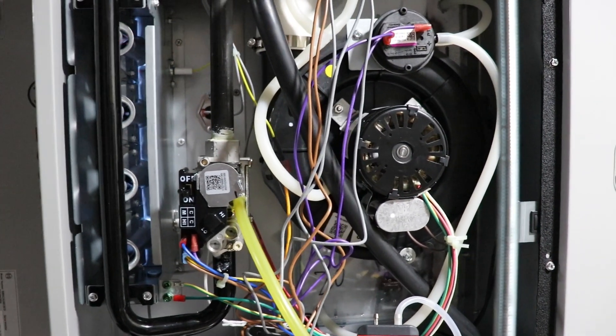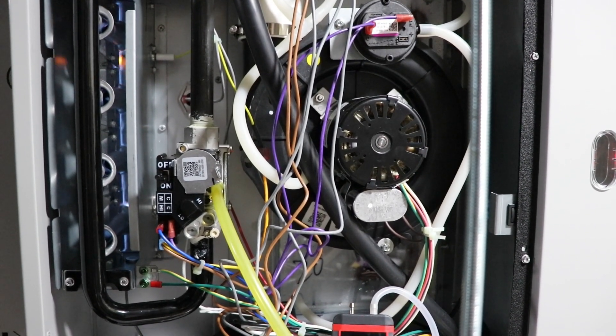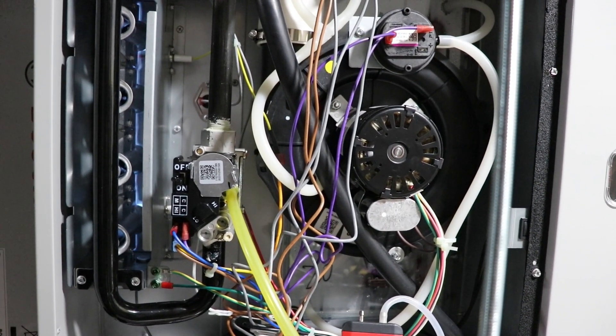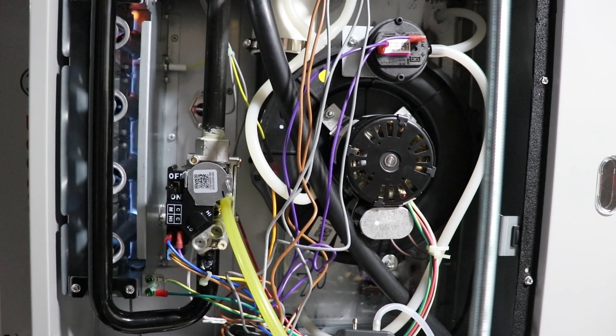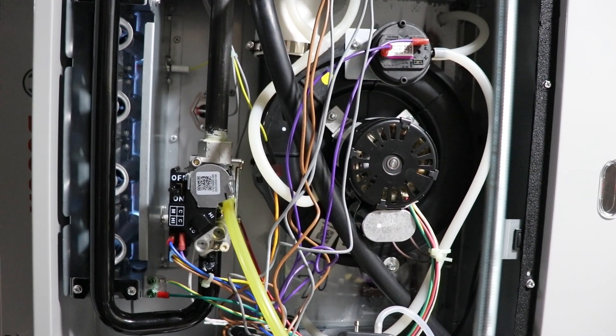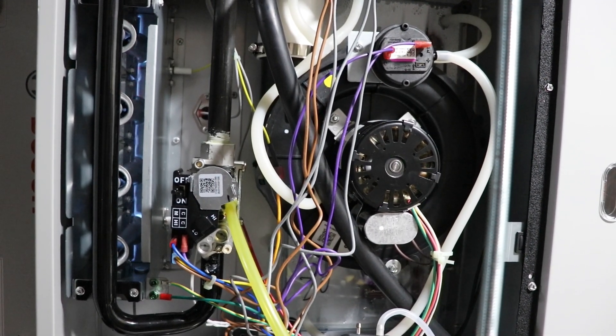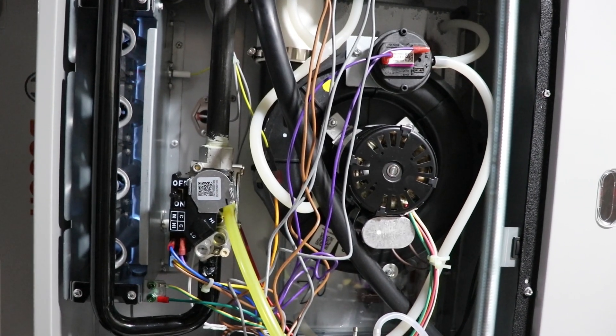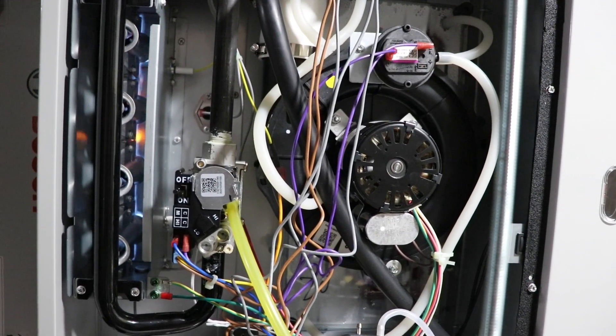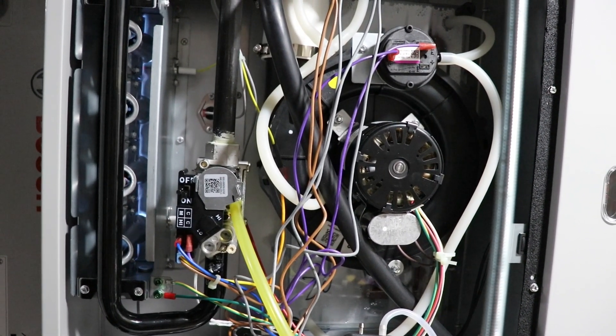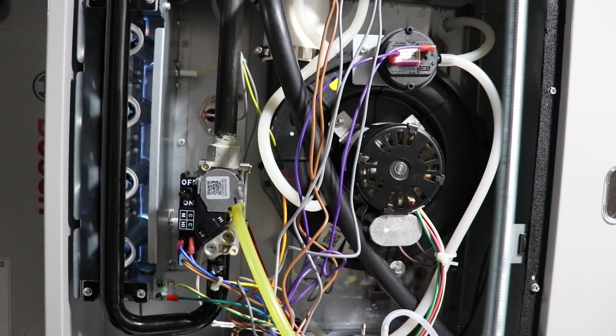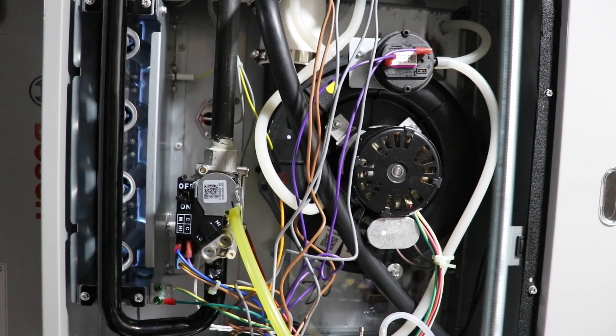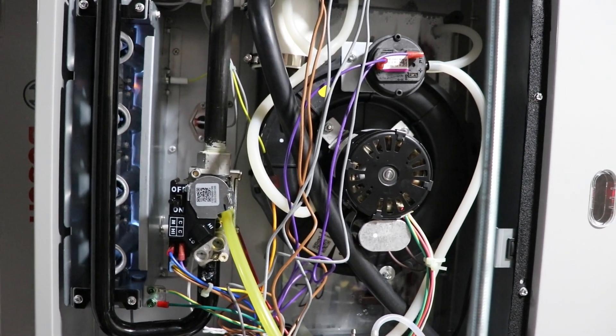It's been down to minus 20, and I changed my compressor lockout temperature to minus 20 because the Bosch IDS B20 is able to do that, whereas some of the other models, like the plus and the entry model one, can only run down to minus 15 Celsius. But it really didn't give it any difference because the house temperature was dropping quickly enough that the BTUs coming out of the compressor stage 2 just weren't enough to stop the temperature from dropping, so it just switched over to aux.